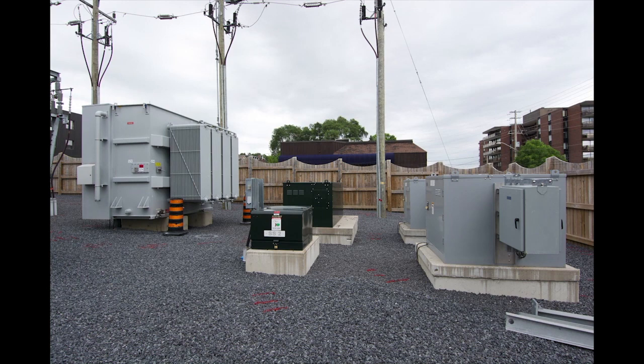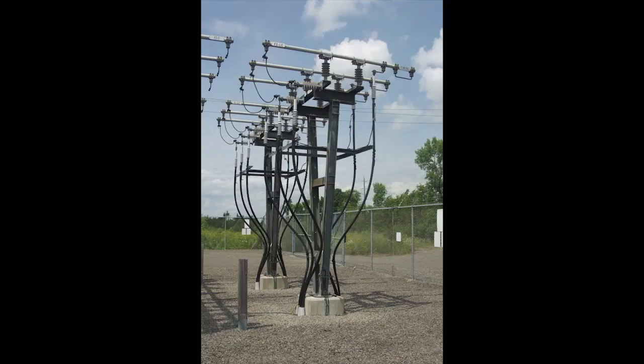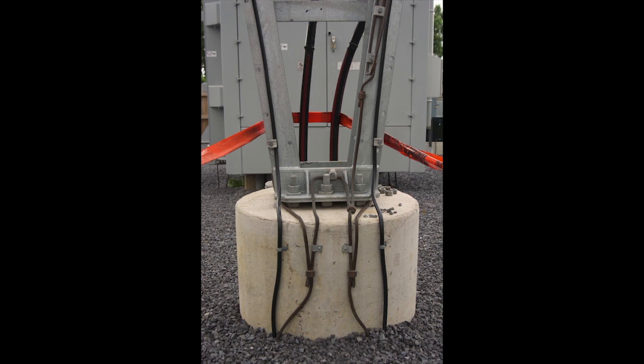When installing the MUS at a U12 station, the MUS high-voltage conductors are connected to the transition pole. The MUS feeder cables are connected to the item 905 exit structure. The neutral from the MUS is connected to the station neutral on a bus bar. Everything in between the transition pole and the exit structure is isolated.